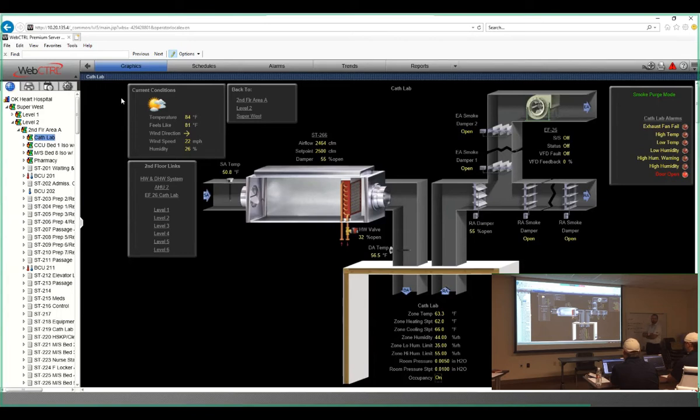And the smoke evac dampers are not reading correctly? Because they should be closed under normal operation. Yes, there was something that got flipped, I'll have to go look and see. Back when they were doing the testing on it the last time with the fire control, I think they ended up switching the contacts we were actually monitoring for some reason. So I'll look at that. We'll add that to our follow-up items, make sure that gets corrected. Because they're actually closed, but we wouldn't be able to maintain that pressure.